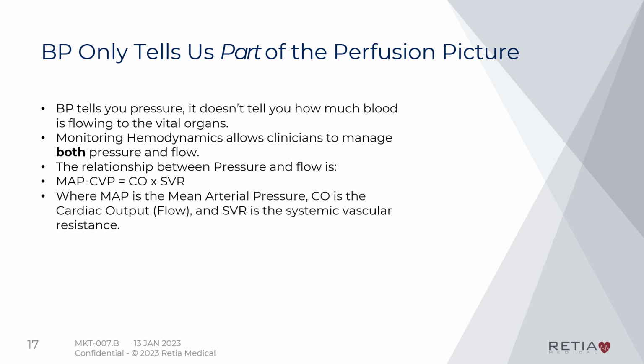systemic vascular resistance. MAP and cardiac output sometimes follow each other. This typically occurs when SVR is not changing, which leads to the common misconception that managing pressure or MAP is the same as managing flow or cardiac output or stroke volume. This is what other cardiac output monitors often do. However, in most critically ill patients, pressure and flow are decoupled due to changes in SVR because of the use of pressors or vasoactive agents naturally produced inside the human body. That is why, to determine flow, the MBA, or multi-beat analysis algorithm, was designed to accurately detect changes in SVR.